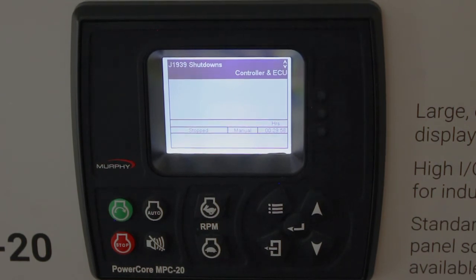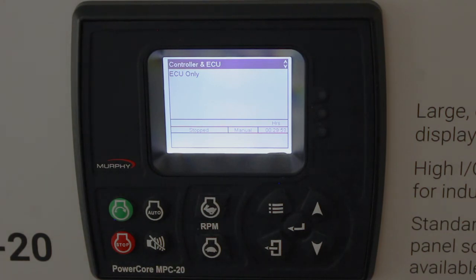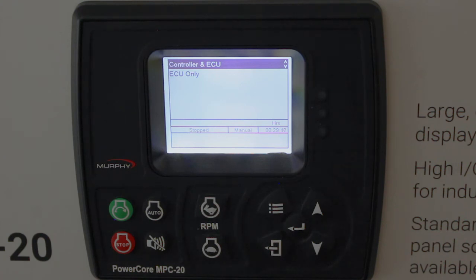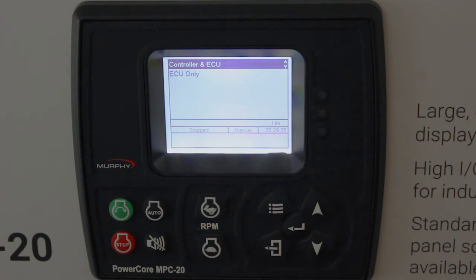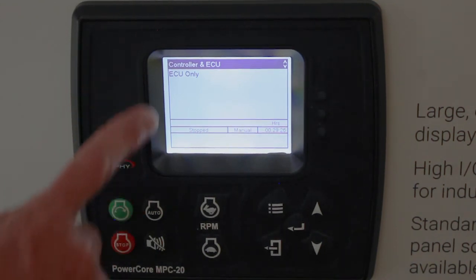The J1939 shutdown menu defaults to 'control and ECU.' That means when dealing with an ECU on an electronic engine, the ECU or the controller will signal a shutdown on a red code. If you only want the ECU to do shutdowns, you would choose 'ECU only.' In that case, the controller will show a red code being broadcasted by the ECU, but it won't act on it — it's up to the ECU to do the shutdown. It defaults to controller and ECU, but you can choose ECU only.